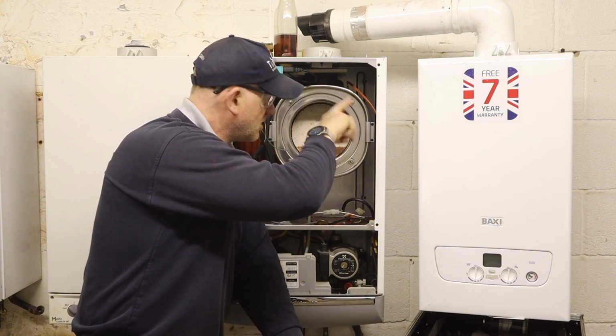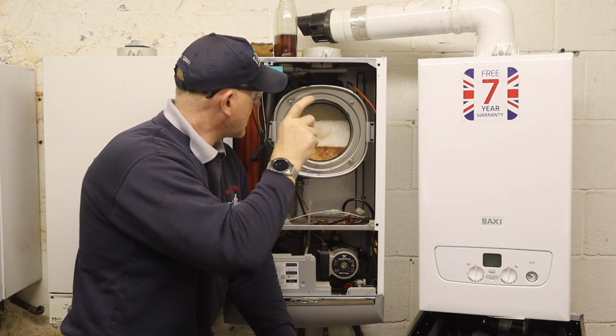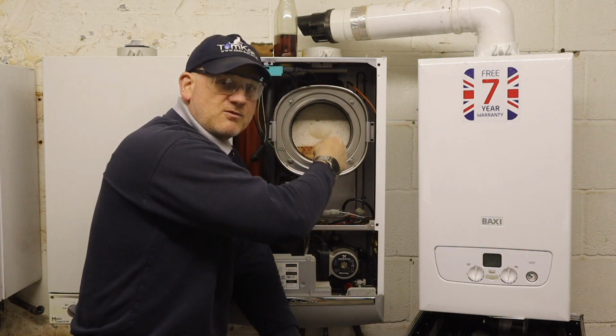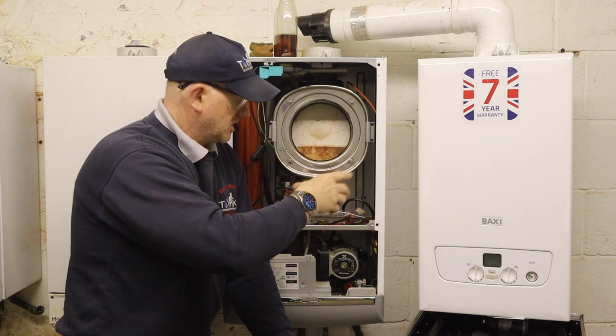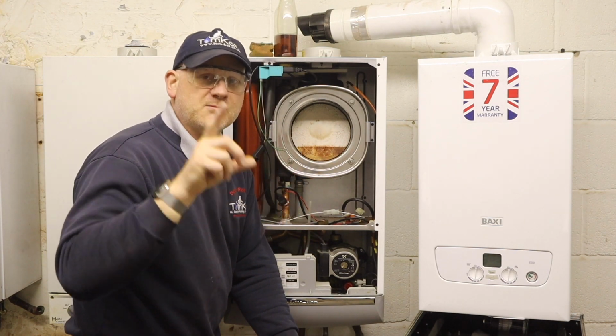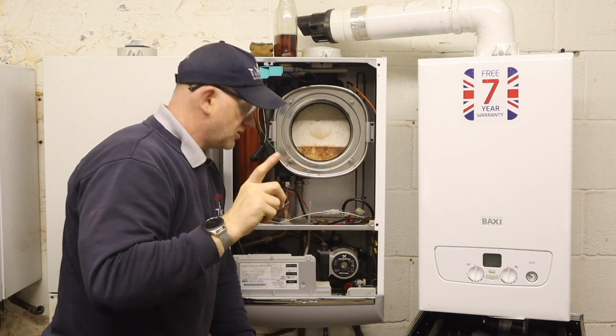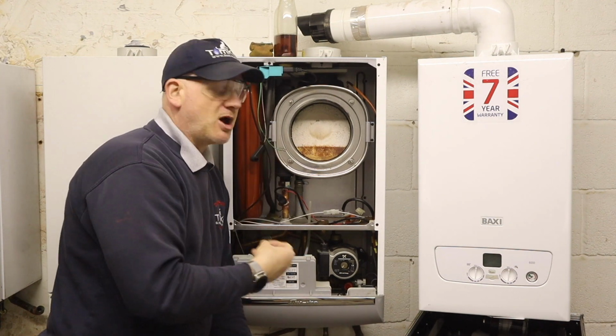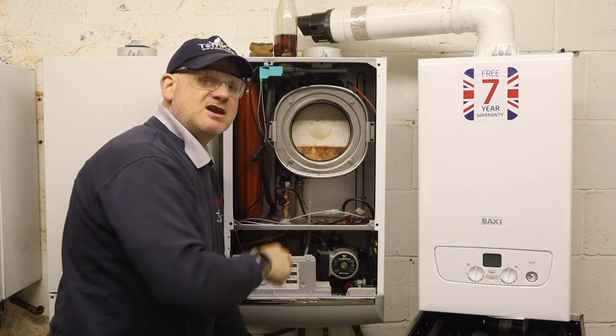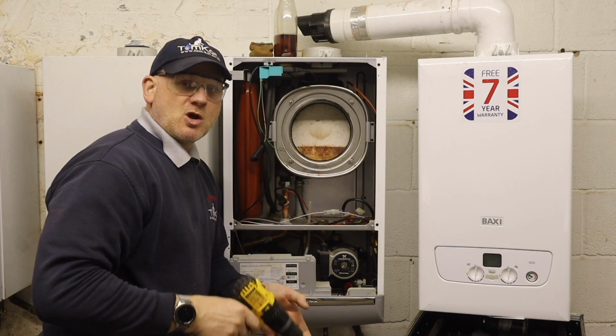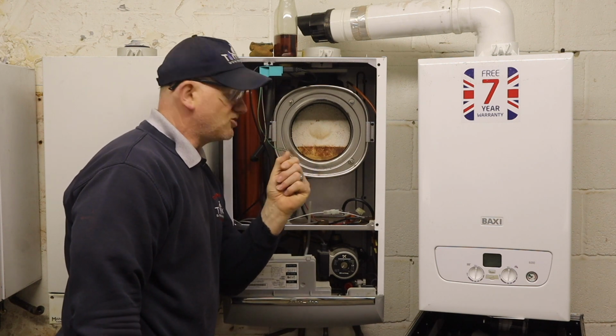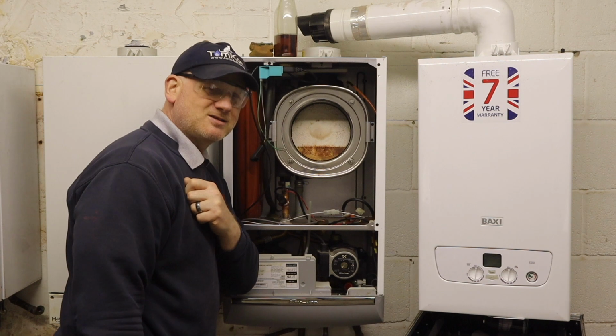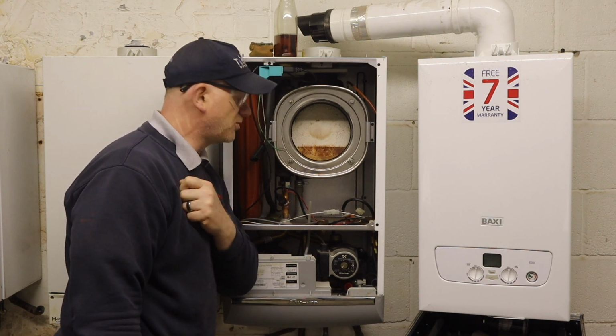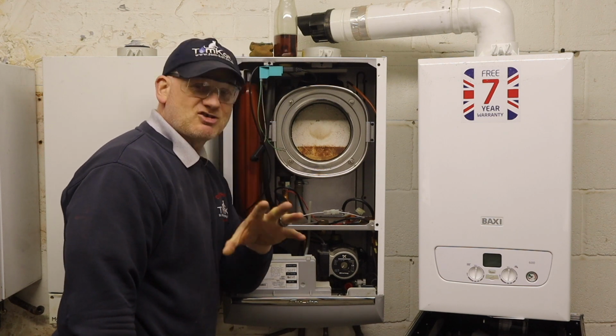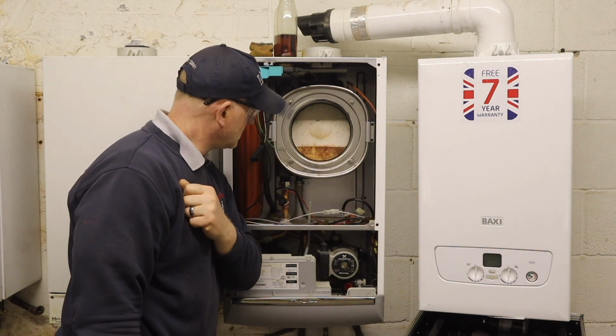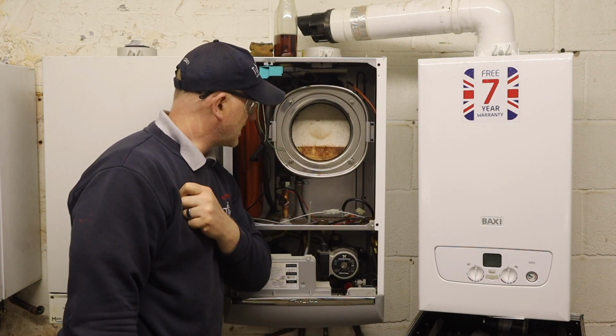Once you've done all this cleaning, make sure you get a spray bottle with clean water, spray all the way around and pour water in so it gets rid of all the debris. Then clean out the condensate trap, otherwise you'll be leaving debris in the bottom which could end up blocking it and giving you a tide mark like this. If you take a heat exchanger out and see a tide mark like that, it's a good indication the condensate trap has blocked up at some time in the boiler's life. I can't stress enough, guys, make sure you don't damage that heat shield at the back, otherwise you'll be replacing it.